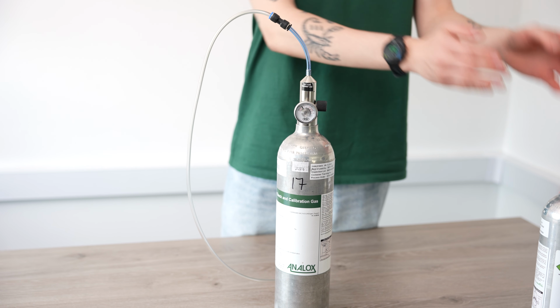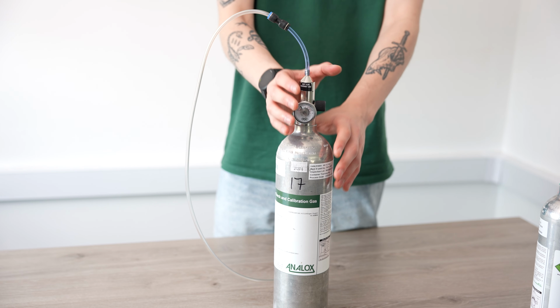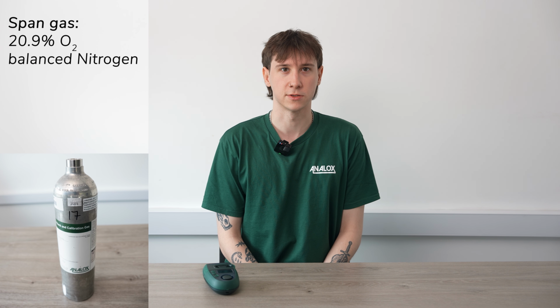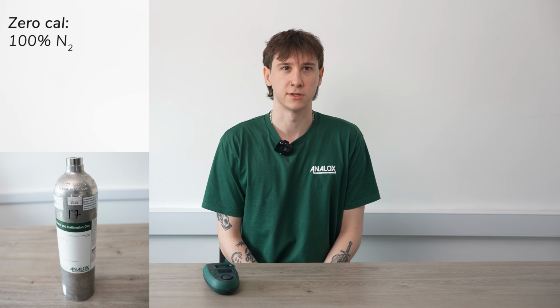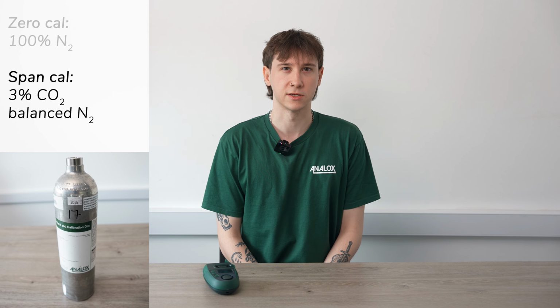To calibrate these sensors we will require calibration gas. For O₂ we only require a span gas of 20.9% O₂ balanced nitrogen. You can also complete this calibration in fresh air if you do not have the required gas. For CO₂ you require 100% N2 for the zero calibration and 3% CO₂ balanced nitrogen for the span calibration. You will also require a regulator and the push-in adapters provided with the Aspida.